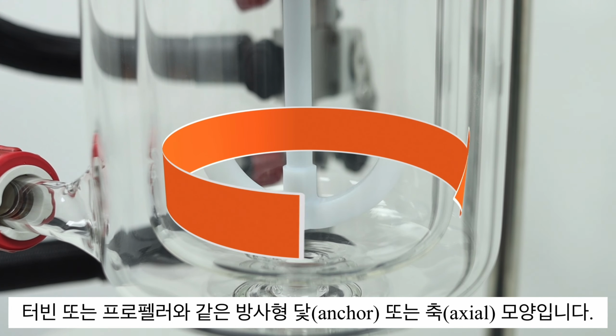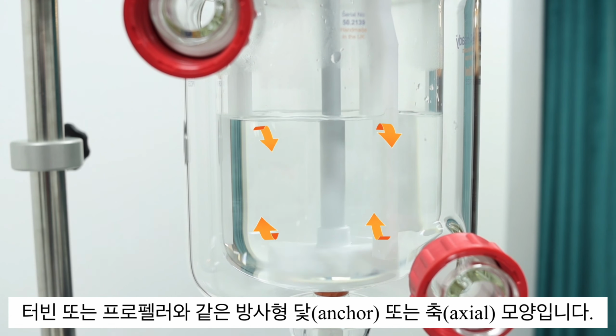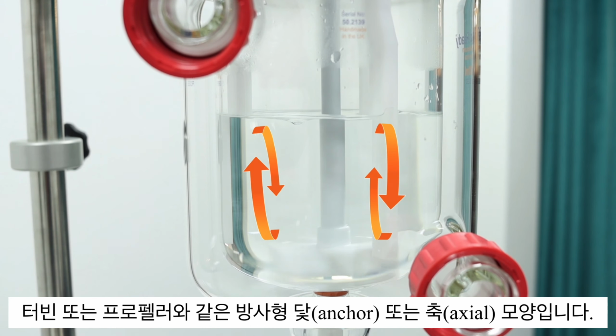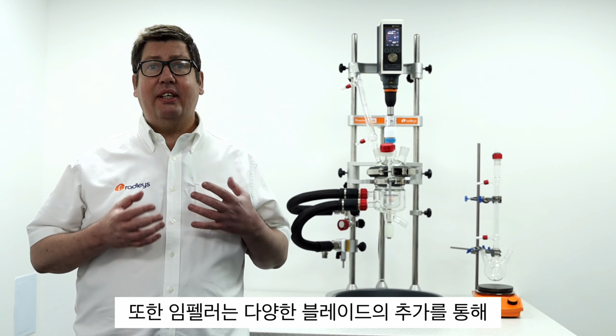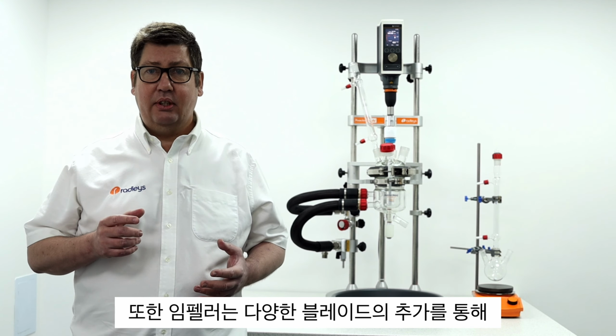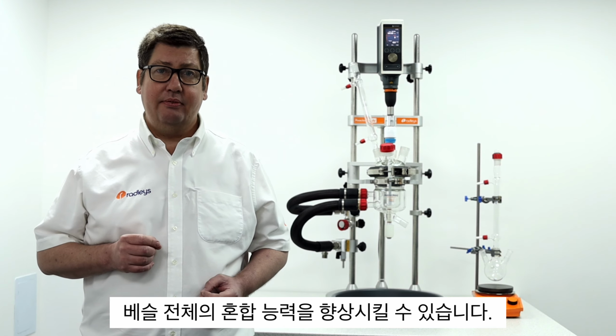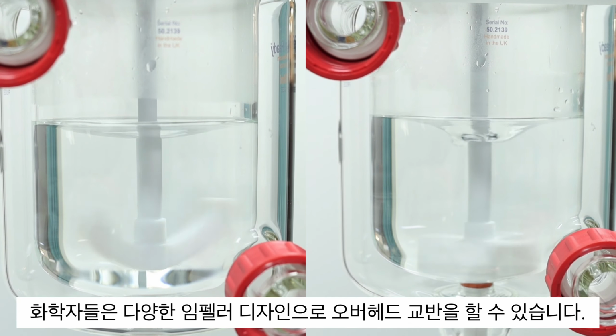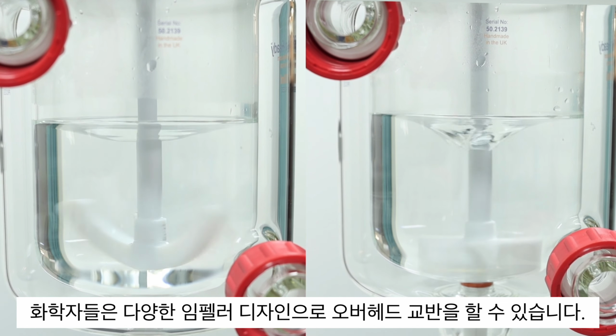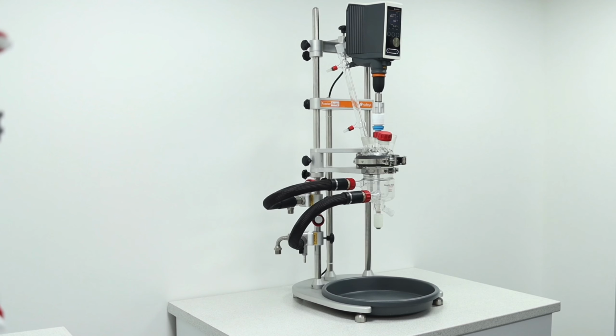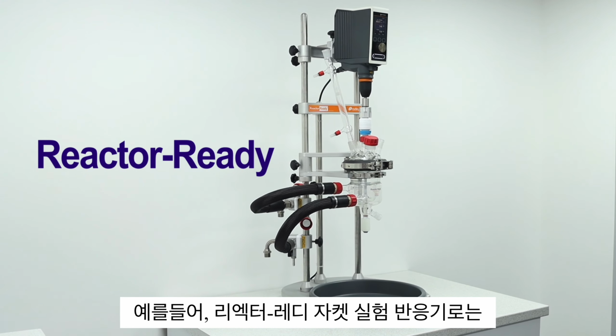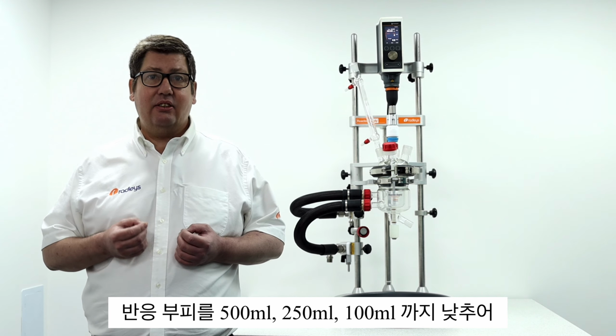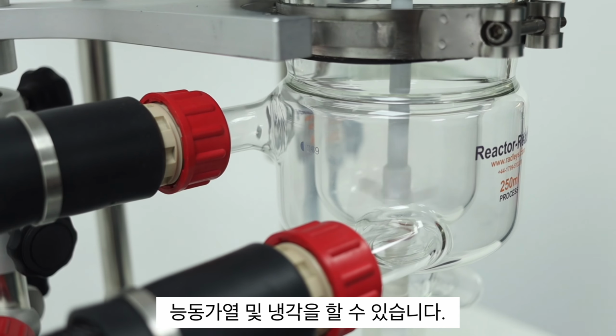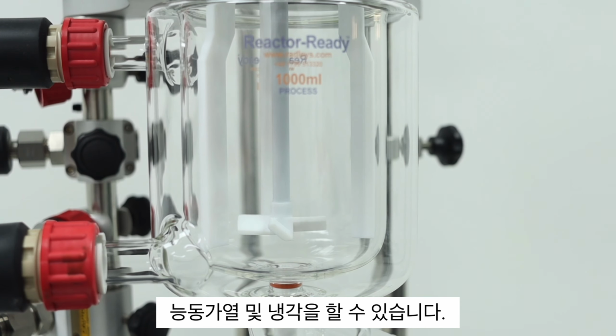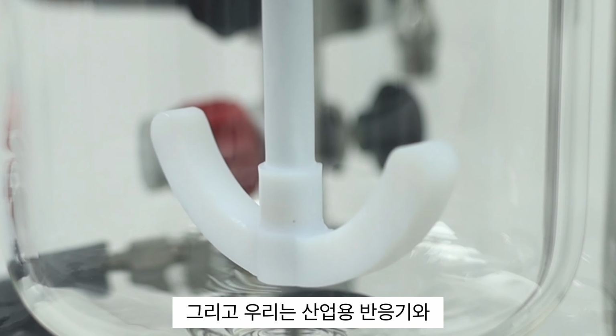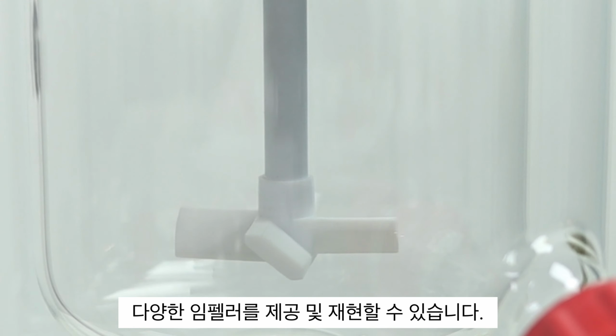For example, radial, like the anchor, or axial, like the turbine or propeller. Impellers can also have additional blades along the stirrer shaft to improve mixing throughout the vessel. The use of jacketed lab reactors enables the chemist to use overhead stirring with a choice of different impeller designs. For example, with reactor-ready jacketed lab reactors, we're able to offer active heating and cooling on reaction volumes down to 500ml, 250ml, 100ml, and be able to replicate the geometry of industrial plant reactors with a range of stirrer impellers available.